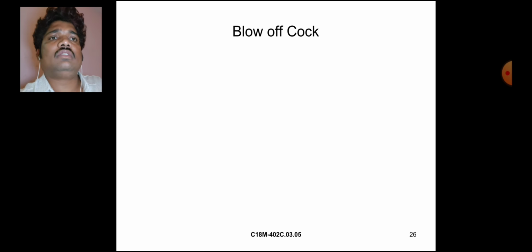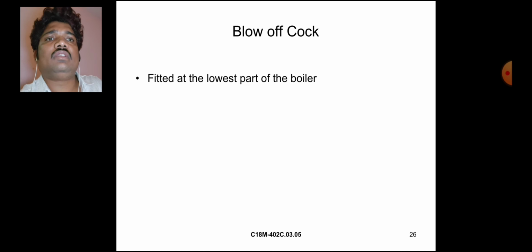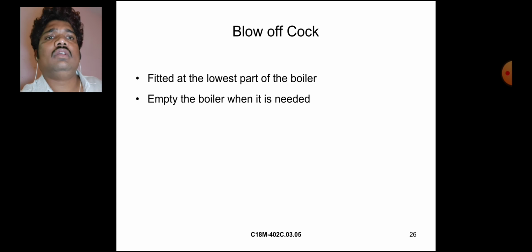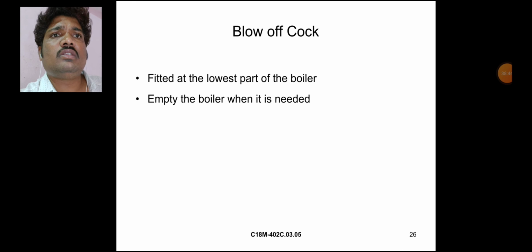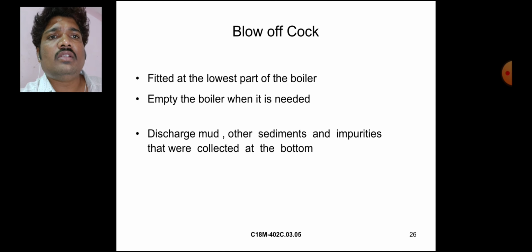Blow off cock. We discuss the blow off cock. It is fitted at the lowest part of the boiler. It is used to empty the boiler when needed, and to discharge mud, other sediments and impurities that were collected at the bottom.